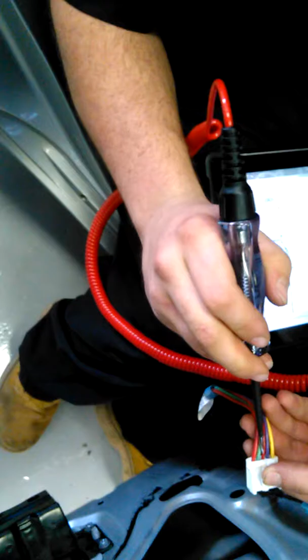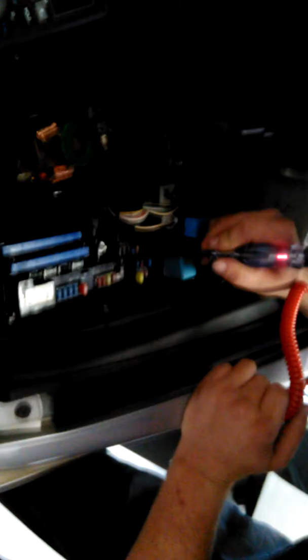So this is where we need to check the fuses to make sure we have power. Let's go to the front and check the fuses. I need to find a good ground here. That's how we're going to test the fuses, making sure they're all pressed in. See that? Good fuse. See, that's a little loose there. This little fuse here is a little loose. This one is loose, but it's not blown.